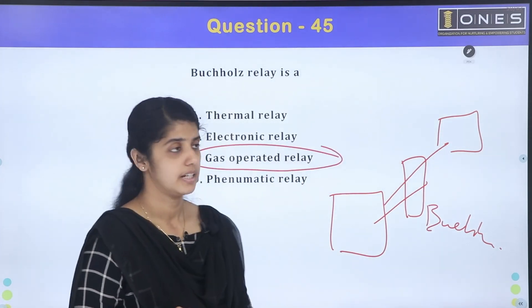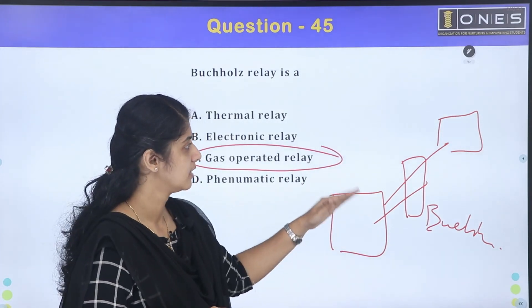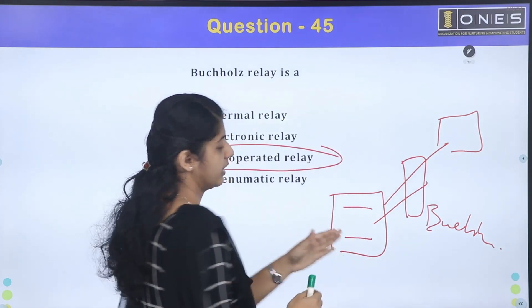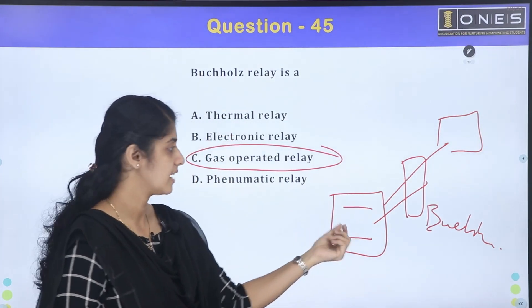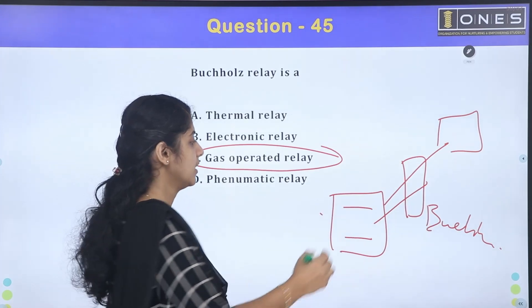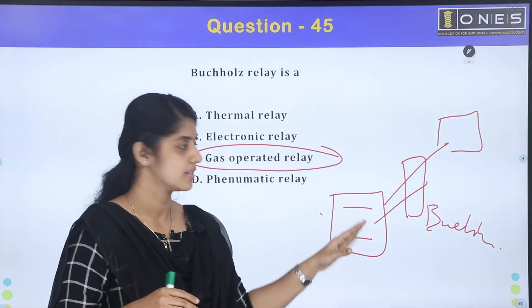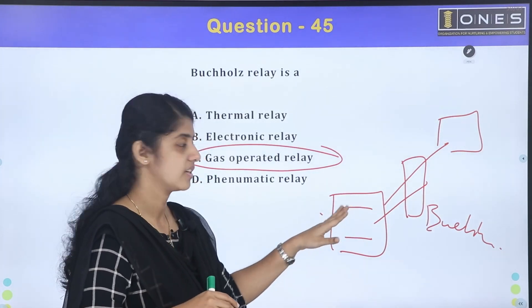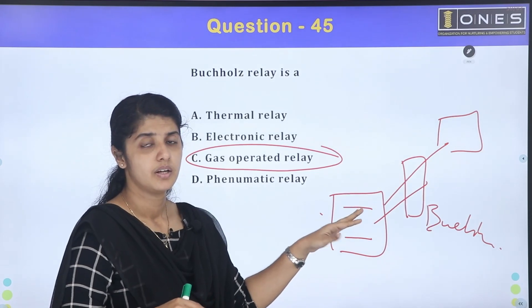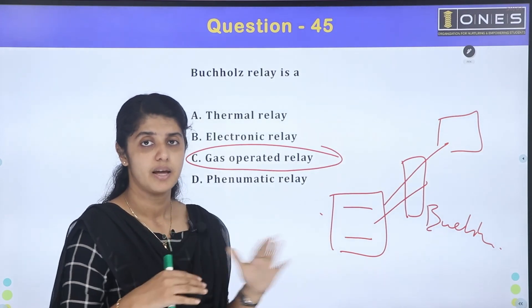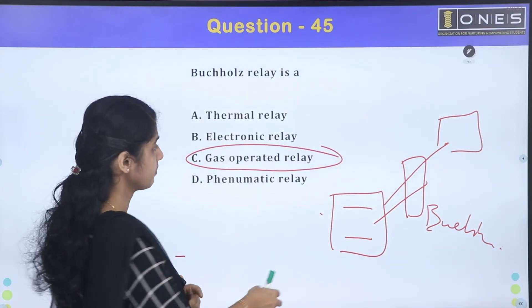The Buchholz relay is activated under fault conditions and uses a gas-actuated mechanism. It operates in two stages — first a warning alarm, then a trip signal — making it a gas operated relay.